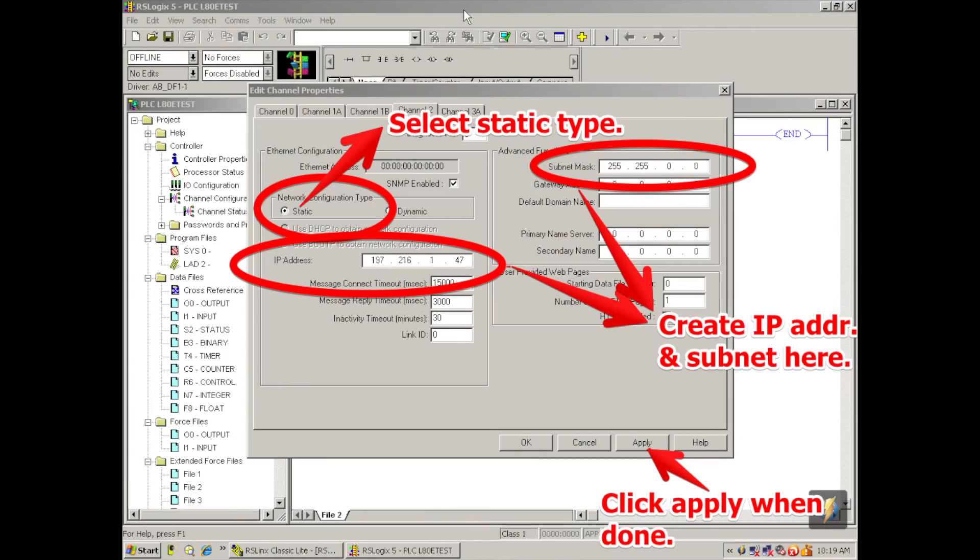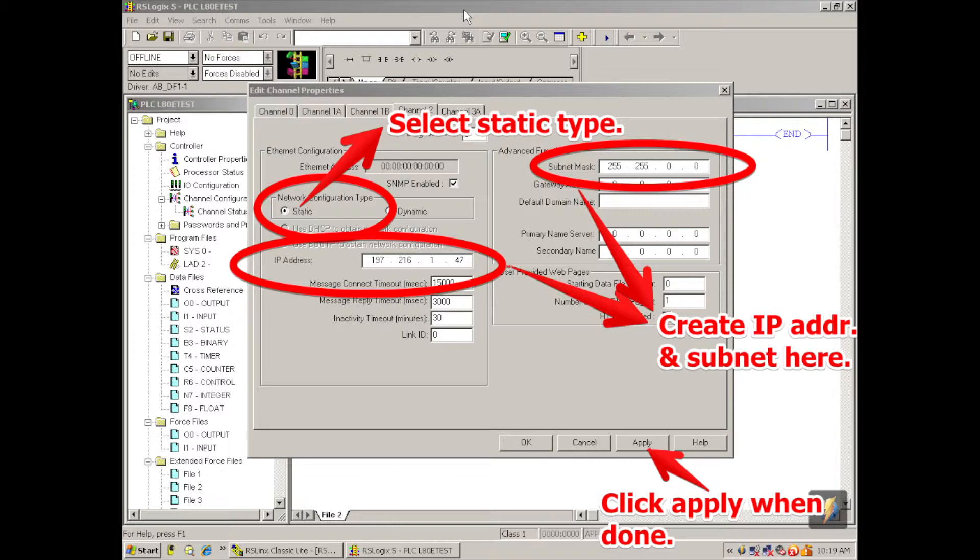Now once I go to channel 2, the window is going to have a bunch of information that's grayed out that you're not able to edit. Okay, so on the left hand side about half way down it says network configuration type. We want to select static. Then the IP address, subnet mask and gateway addresses, they all open up so that you're able to edit them.